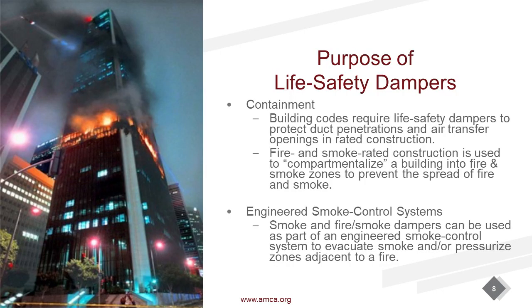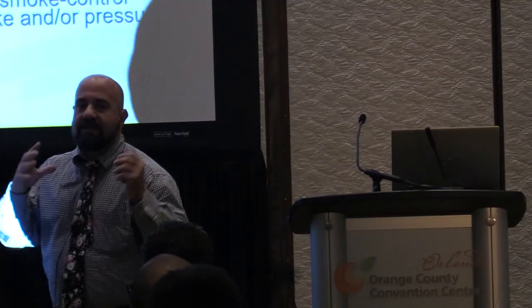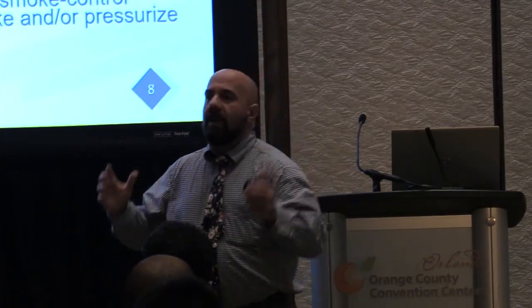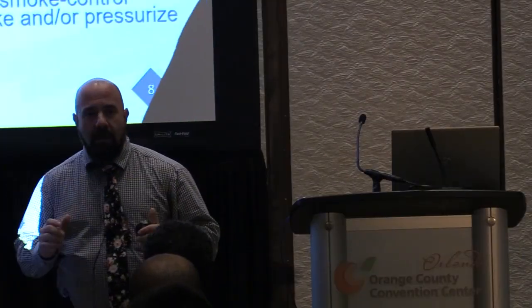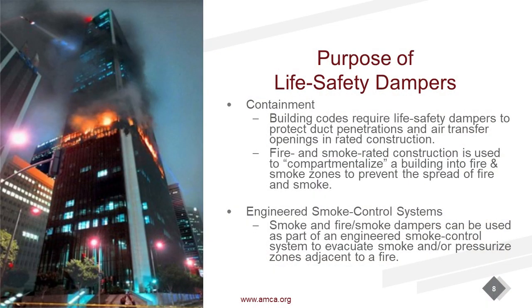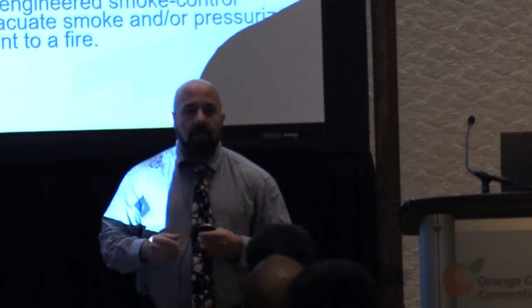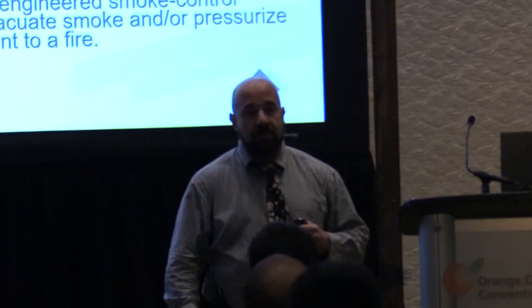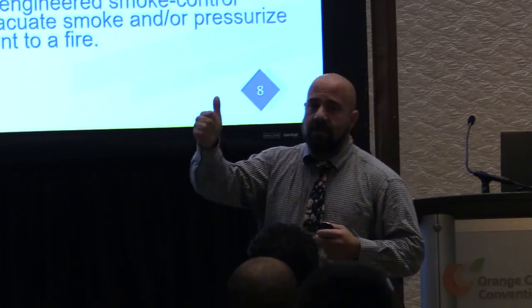So why do we need dampers, right? We know the code requires them. They operate on a very simple principle, containment and smoke control, right? Containment compartmentalizes buildings. We create areas of refuge. We create fire-rated barriers. We protect rooms from the things that are inside of them. Control the movement of smoke, right? Very large buildings, high concentrations of occupants in the buildings, places where it's hard to egress or evacuate and escape a fire. There's certain code requirements, so we need to control the movement of smoke as well. And in doing that, we save lives and we save property.